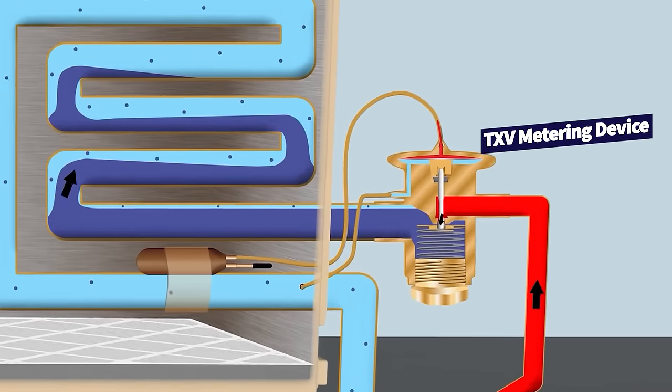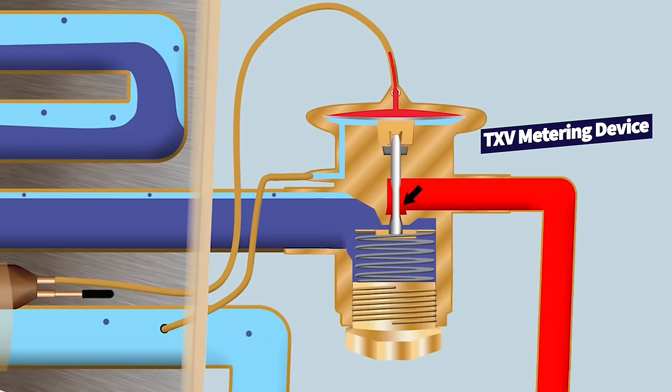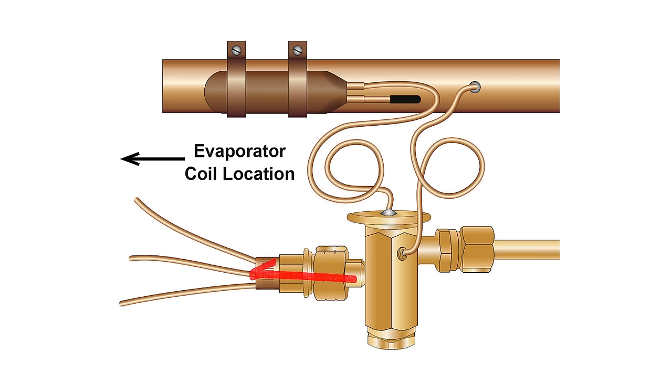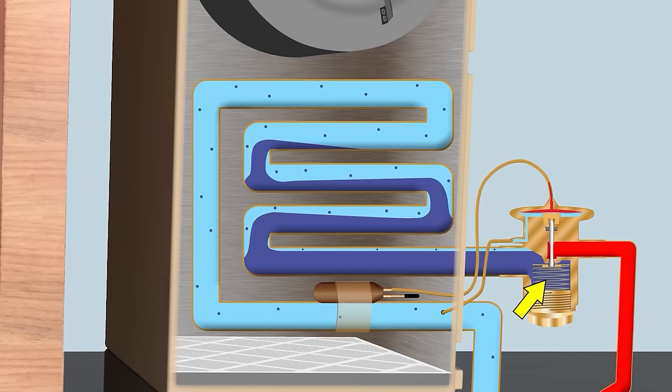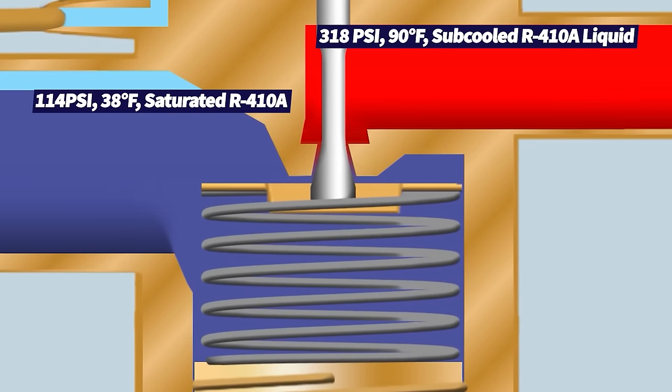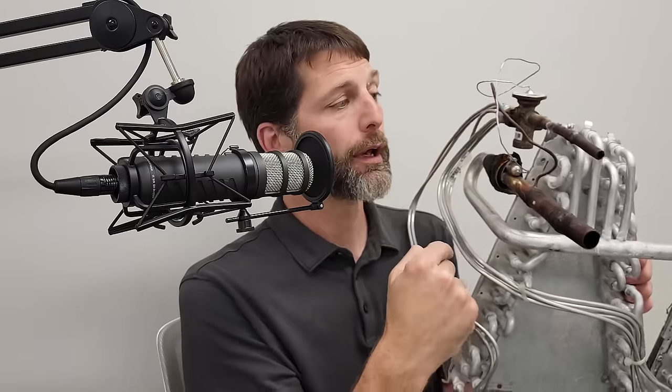You have high pressure refrigerant entering into the restriction device — also noted as a metering device — and then it travels through the distributor tubes into your indoor unit's coil. The whole point of this restrictor is to lower the pressure of the high pressure refrigerant. When you lower the pressure, you're going to be lowering temperature as well. The job of this indoor unit coil is to be a heat transfer device between the refrigerant traveling through the tubes and the air crossing over the fins.